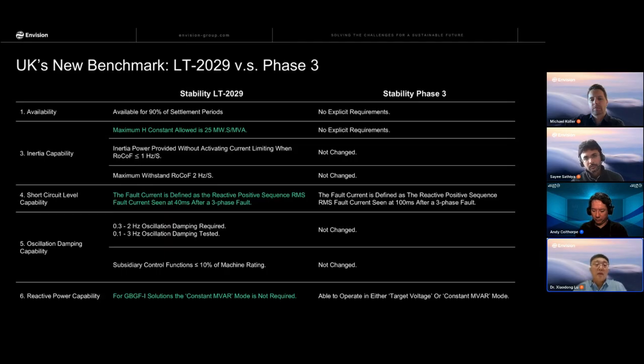The third major difference is the reactive power mode. Previously, the grid forming BESS, especially the grid forming BESS plant, was required to work in either target voltage or constant reactive power mode. Now it's only target voltage. Constant reactive power mode is no longer required. It makes sense since grid forming BESS is a voltage source. It helps to stabilize the voltage.